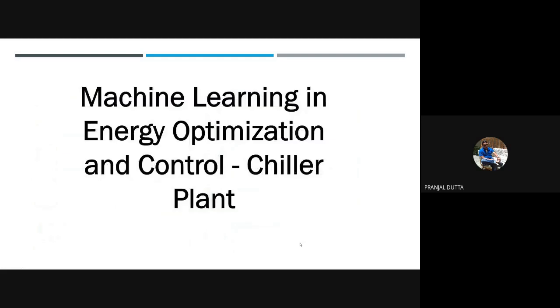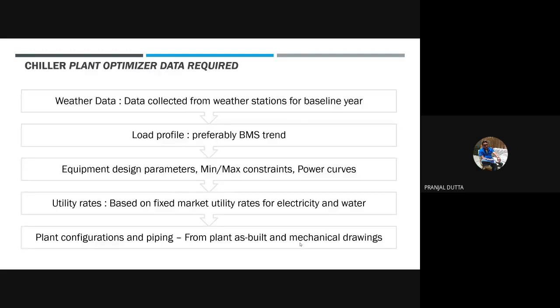Now we will go to the actual application where machine learning is used for chiller plant optimization. I cannot show you the actual layout in the software because it is intellectual property, so I will give some basic layout of the applications. Chiller plant optimization uses this type of data. Basically, weather data is required because chillers mostly depend on the weather. Whether they operate at low or high load depends on the weather in that particular area.